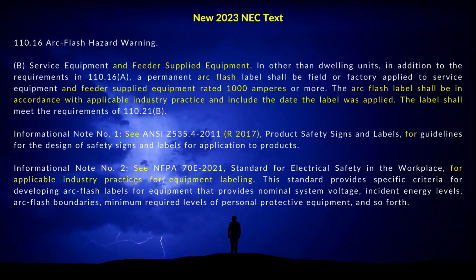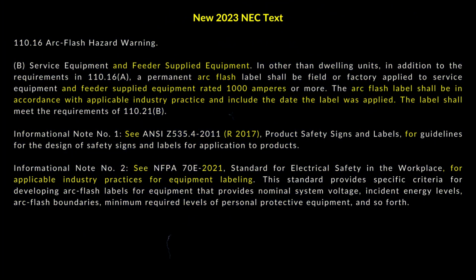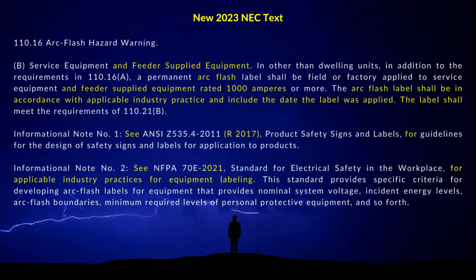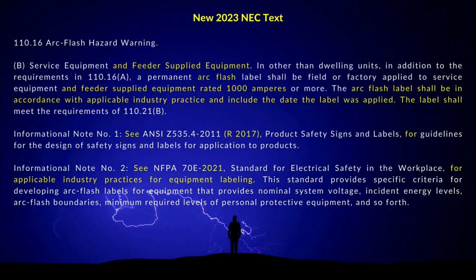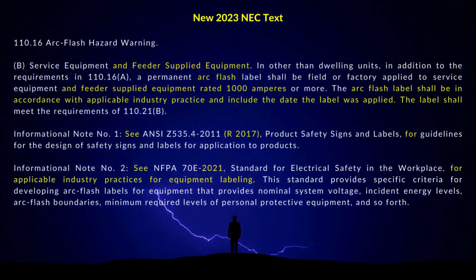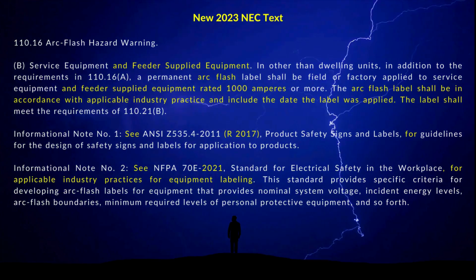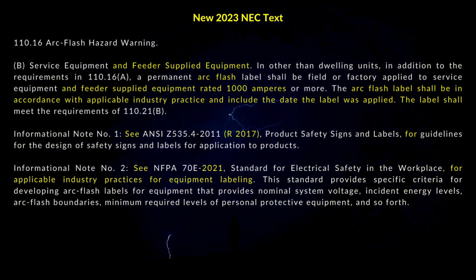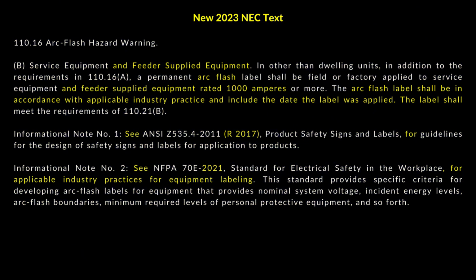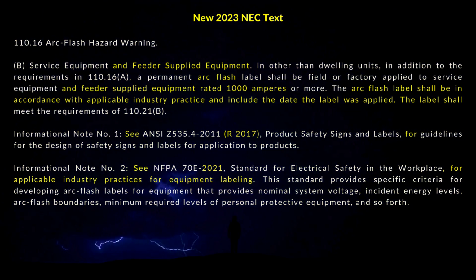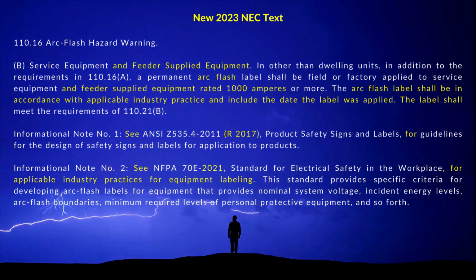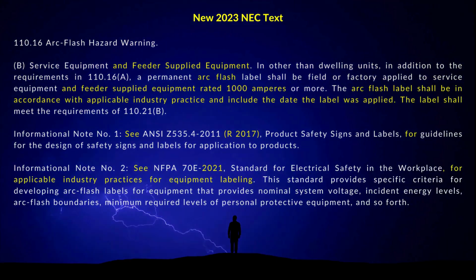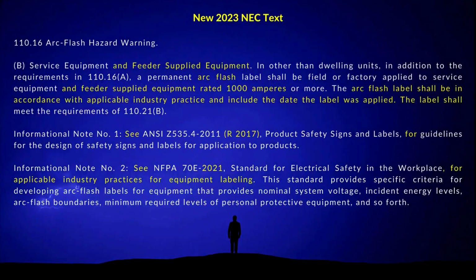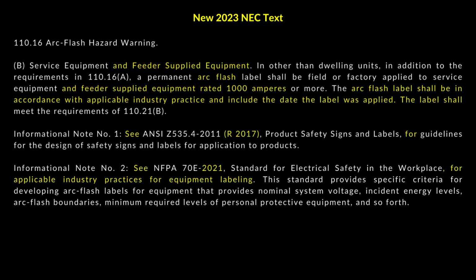The new 2023 NEC text for 110.16(B) states that, in other than dwelling units, in addition to the requirements in 110.16(A), a permanent arc flash label shall be field or factory applied to service equipment and feeder supplied equipment rated 1000 amperes or more. The arc flash label shall be in accordance with applicable industry practice and include the date the label was applied. The label shall meet the requirements of 110.21(B).